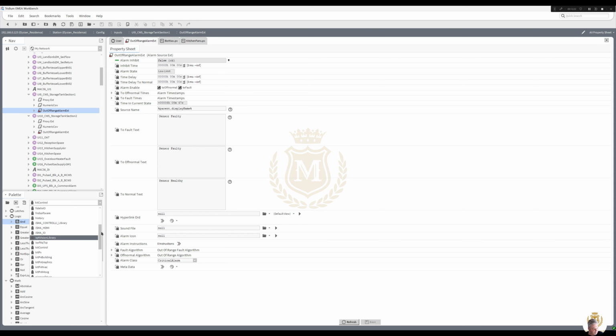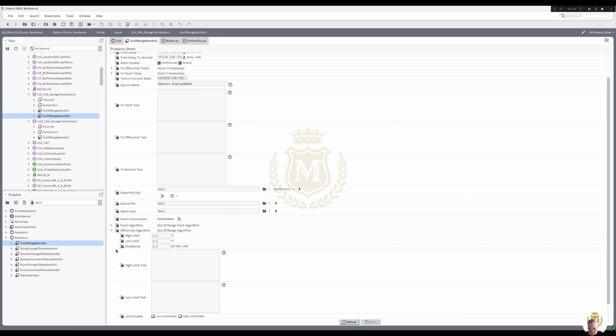So kit, histories, alarms and extensions, and we'll go for out of range alarm again. This is going to put a 1 at the end of this now, like so. And this time I'm not bothered about the low, but I am bothered about the high. I'm going to put 20 degrees with a dead band of 1, that's 0.5 either way.